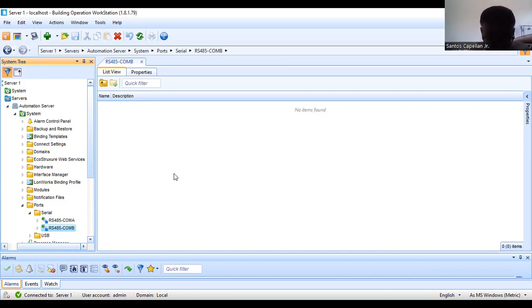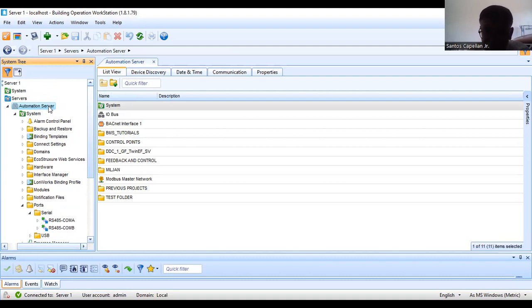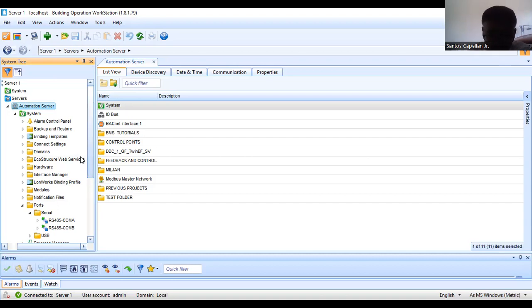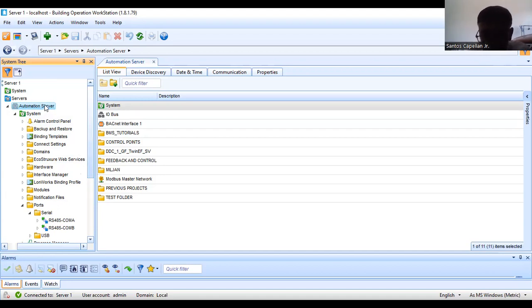When doing software integration, first check the specification to identify any third-party system such as variable frequency drives. You need to know how to get information from that device. Check your automation server to see what communication protocols it supports. If it is supported, then you will create the interface. Today I'm going to create the interface for this communication module.